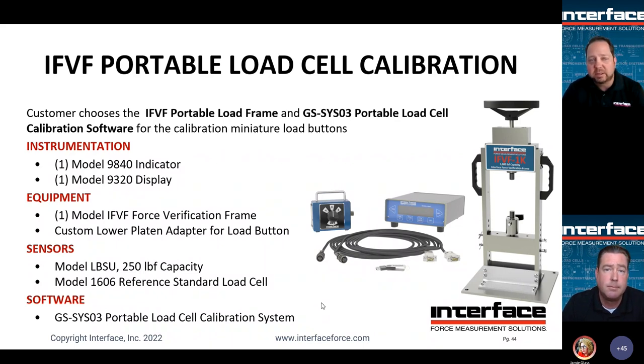And then you can calibrate things such as maybe some load buttons or even some small mini type load cells against a reference standard. So you'd have a 1606 in there. Again, this is a 1,000 pound rated frame. So if you're doing a couple 100-pound loading in a 1606, or if you're going all the way to 1,000 pounds, of course, you'd want to use a 1610. And then you'd use the portable load cell calibration system, GS-SYS03. That system includes the software. Software is really important because it can capture that data, it can do linearization in many cases, and more importantly, it gives you the CalCert. And these are customized CalCerts, company information, company logos, or if you want to only have certain data or additional data reported on the CalCert, of course, the software that goes along with that would do that as well.